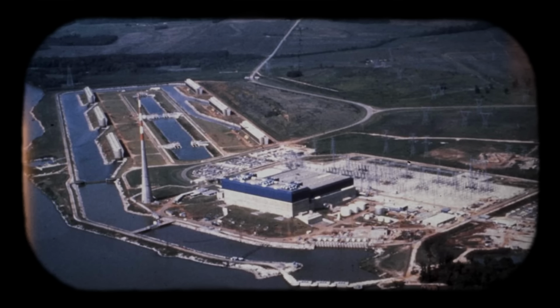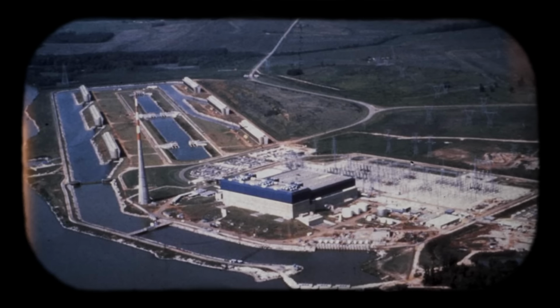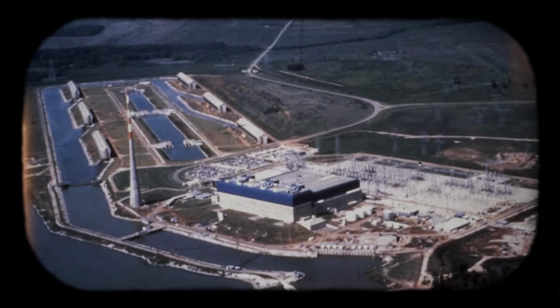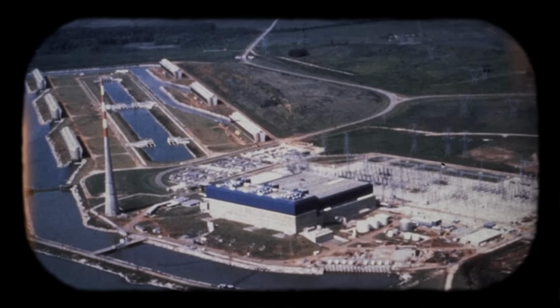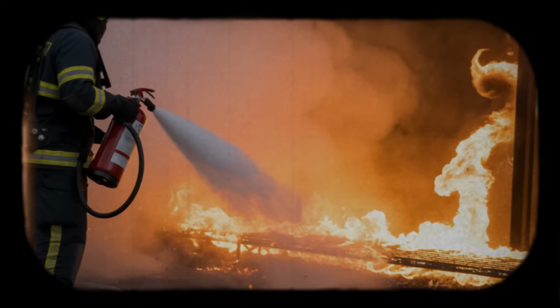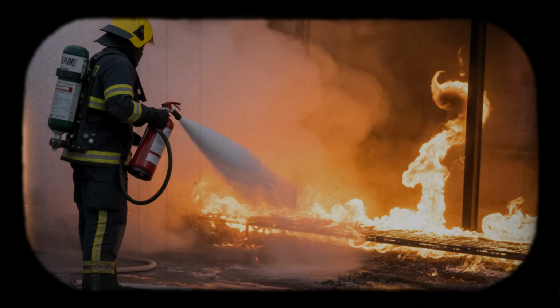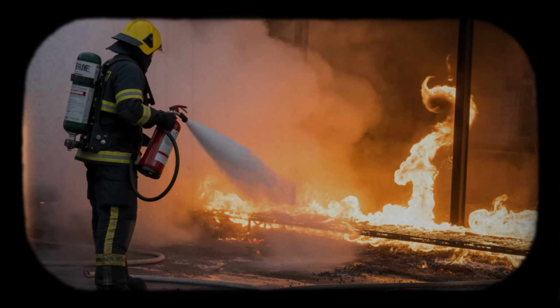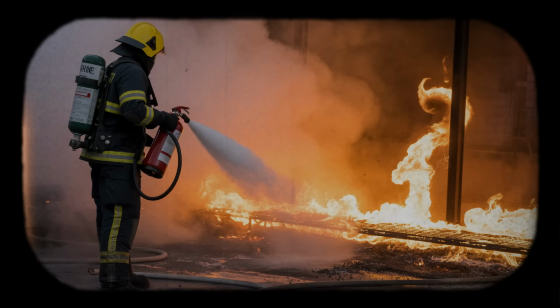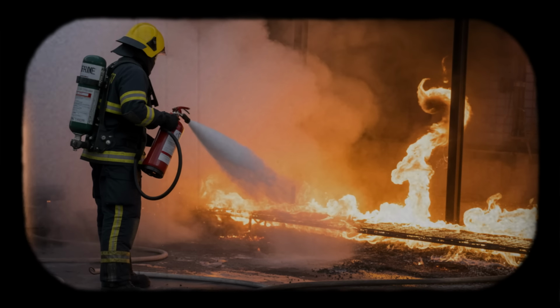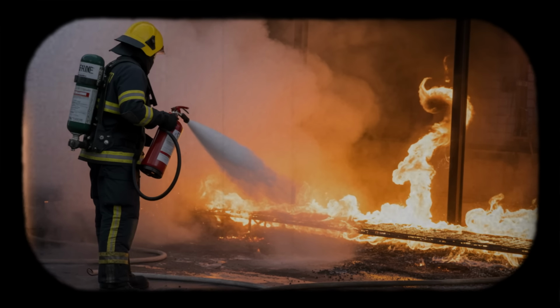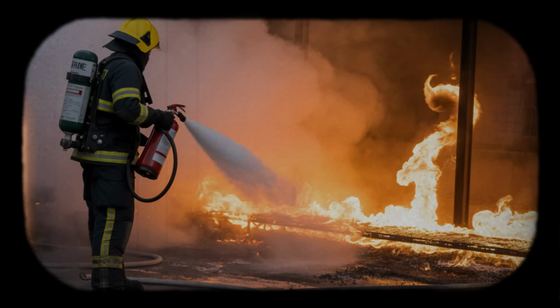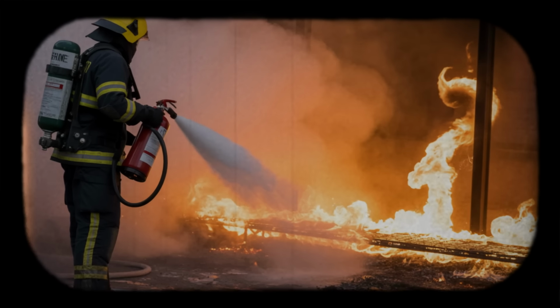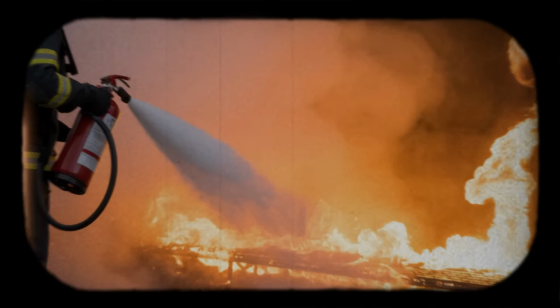Smoke density makes visibility nearly zero. Heat radiates from the cable trays. The fire is not limited to surface combustion. It has penetrated deep into cable bundles where insulation smolders and burns in oxygen-starved pockets. CO2 cannot reach these areas effectively. The nature of cable fires makes them particularly difficult to extinguish. Cables are packed tightly in trays, sometimes stacked 4 or 5 layers deep. Air gaps between cables are minimal.